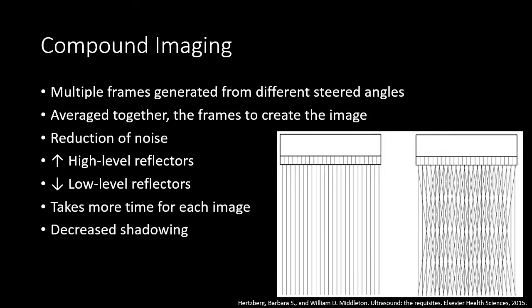Compound imaging involves generating multiple pulses at different angles within the same field of view, then averaging the images generated from each of those pulses to create the final image. This results in a reduction of noise and accentuates high-level reflectors while decreasing the contribution of low-level reflectors. It takes more time per image, resulting in a lower sweep speed and potential lag with real-time imaging. It can also reduce shadowing — which can sometimes be a disadvantage diagnostically, for example when evaluating for a small non-obstructing renal calculus, where turning off compound imaging could accentuate the shadowing.